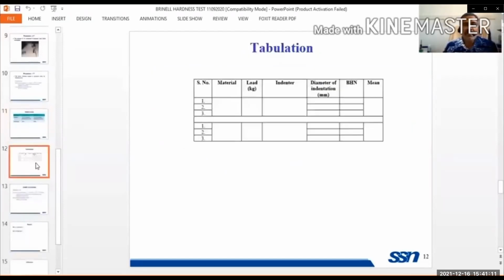And this is a table. In the table, you have to enter all the details. For materials, we have used two materials: one is cast iron, another one is aluminum. The load is 3000 kg for cast iron and 1000 kg for aluminum. We used a 10 mm diameter ball indenter. The diameters you will get from the microscope, and you have to enter the diameter. Here there are 3 diameters given, but we have taken only one diameter.